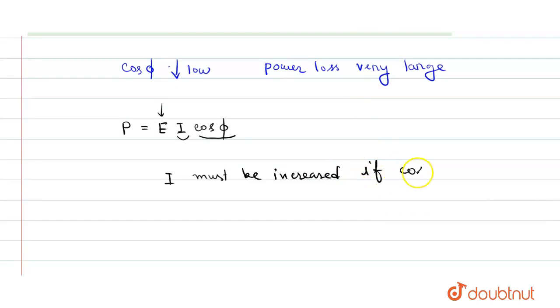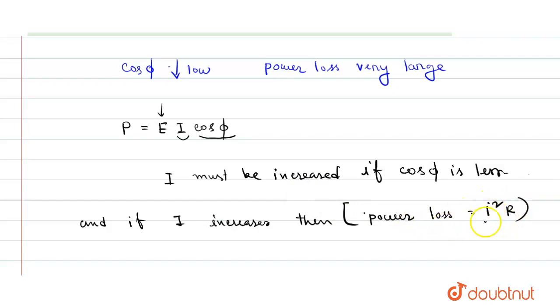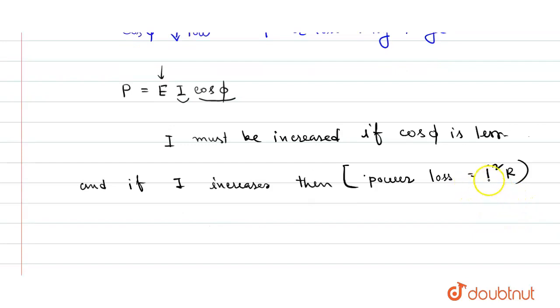If cosφ is less, and if current increases, then heat loss or power loss increases. Power loss is given by I²R. Since power loss equals I²R, and the value of I is increased, power loss will increase. The loss will be very large as it is proportional to the square of the current, so power loss will be very high.